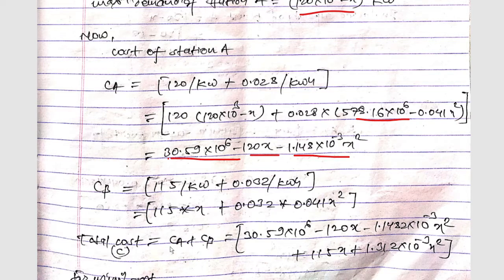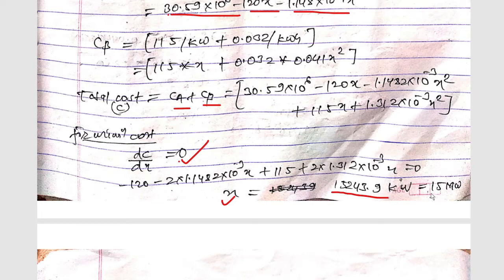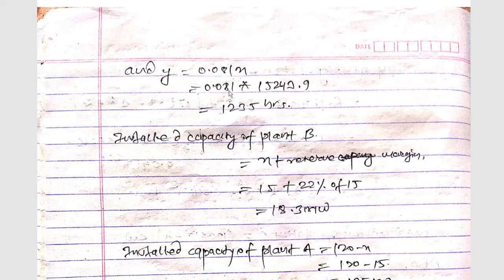The total cost C = CA + CB. For minimum cost, we set dC/dx = 0 and solve. Taking the first derivative and equating to zero gives the value of X, the maximum demand for station B. Solving yields X = 15,243.9 kW, approximately 15 megawatt, and Y = 0.081 × X = 1235 hours.